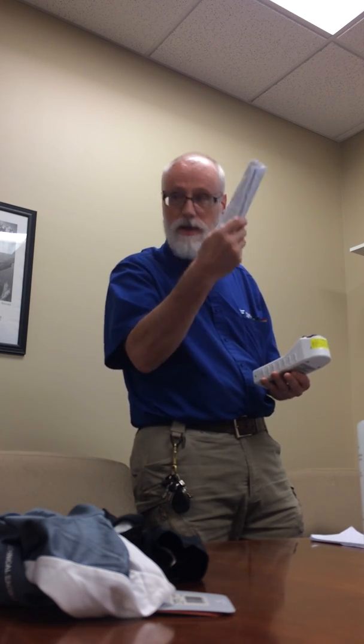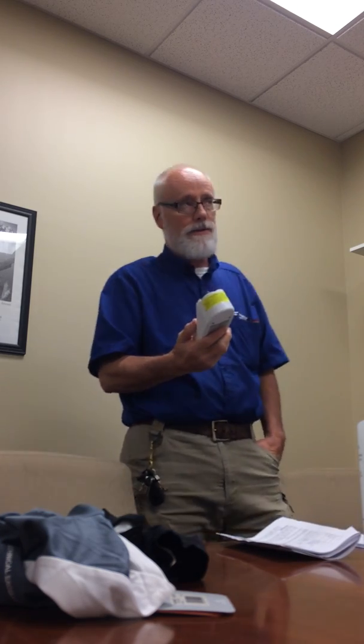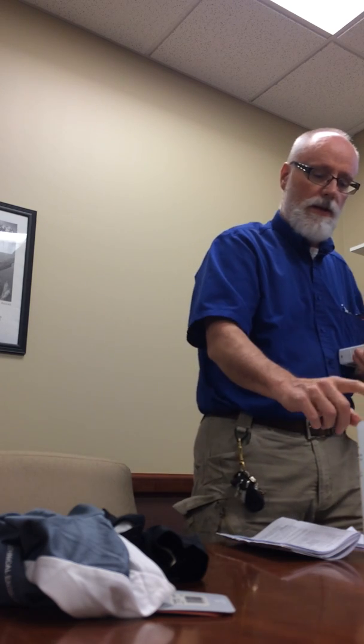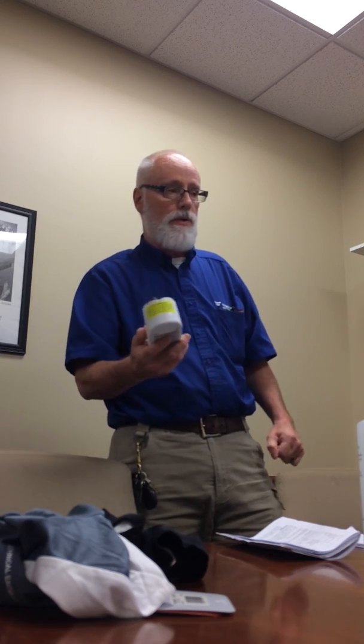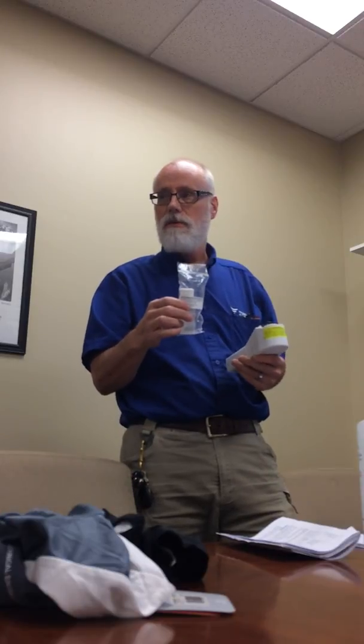As far as our books, the range information is on page 18, wherever the staff are at. If these are on the floor and you're done with calibration at the end of the day, you need to rinse it out with water. We'll probably still have a jug of RO water with the date and time you collected it, and something with a flip-up cap to rinse it out with.